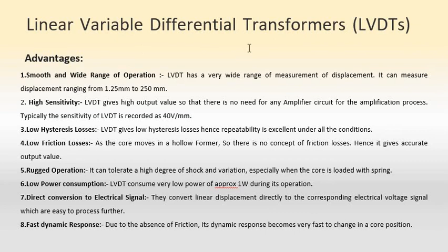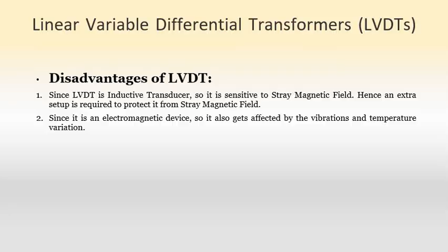Hence an extra setup is required to protect it from stray magnetic fields. There is a chance of an unwanted magnetic field interacting with the area between the primary and secondary, which may also result in a change in the output voltage. So we need to take care that such stray magnetic fields do not enter the area. Since it is an electromagnetic device, it will also be affected by vibrations and temperature variation. So vibrations and temperature variations should also be kept to a minimum.